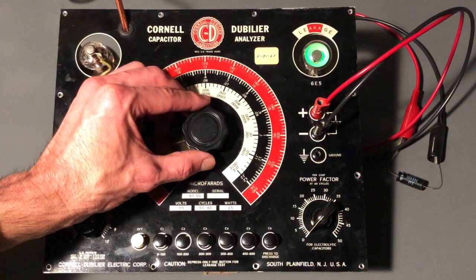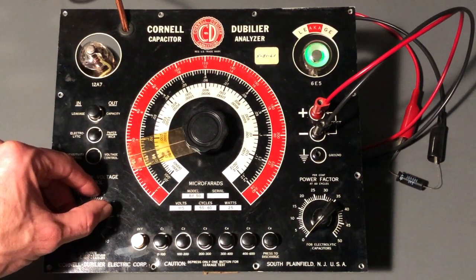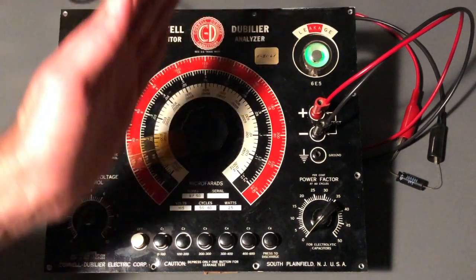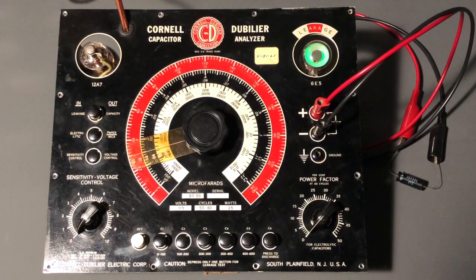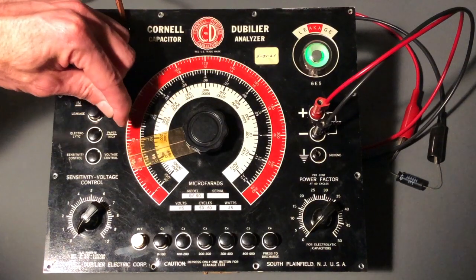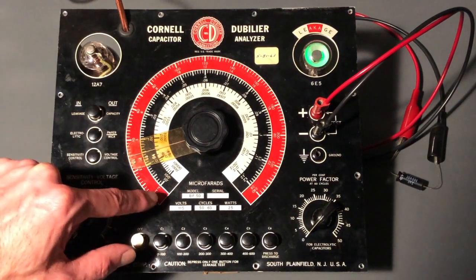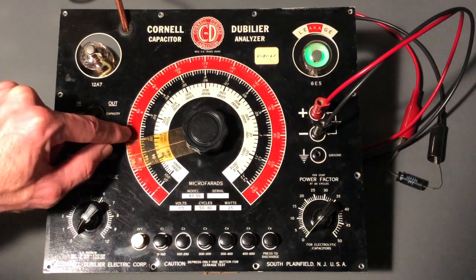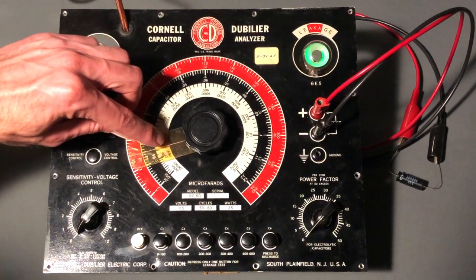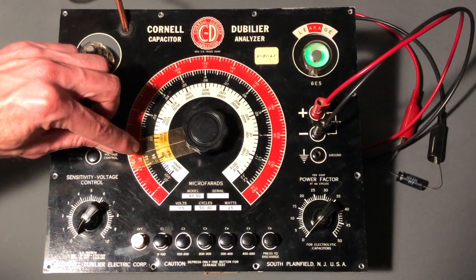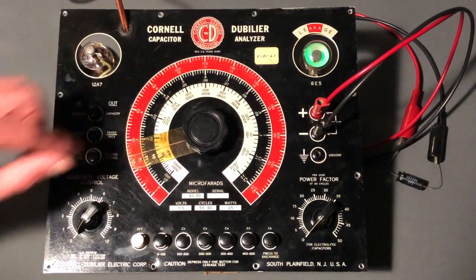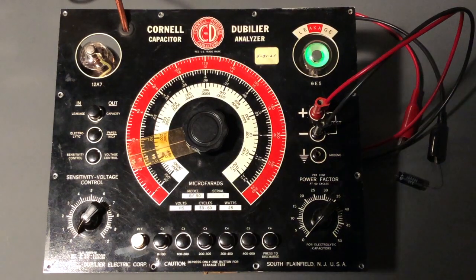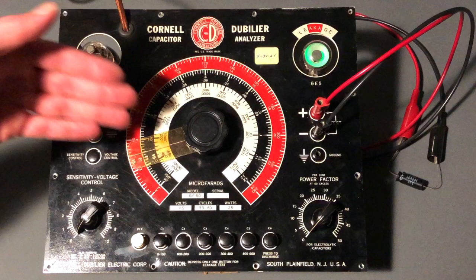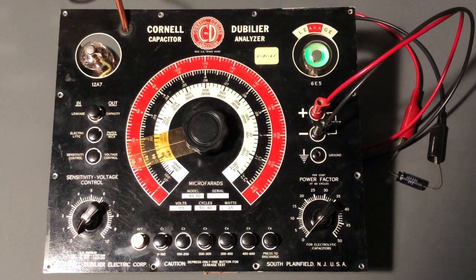I'll do this a second time just looking at the eye tube. It may be a little bit hard to see on the camera right now. But really that looks like the maximum point right there where the eye is open as wide as it will go. So taking a reading right here on the dial looks very, very good, because on the C2 scale, it starts at 0.2, then it goes to 2, and then to 4. So 3 microfarads is right in the middle, and the indicator line is right on the 3 microfarad, and then it's just slightly below it, just ever so slightly below the 3. And that's perfectly acceptable. That capacitor has a tolerance, plus minus around the 3 microfarads. So very, very good that the tester is reading that precise and that accurate. So at this point, the tester appears to be functioning correctly in both the leakage and capacity tests.